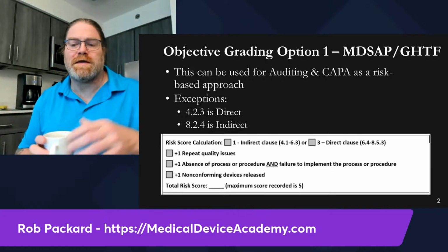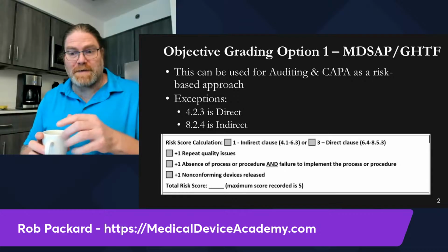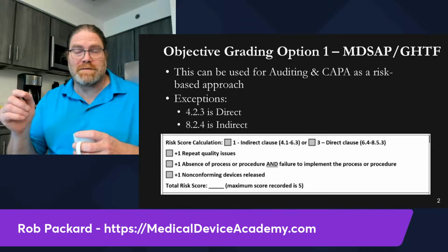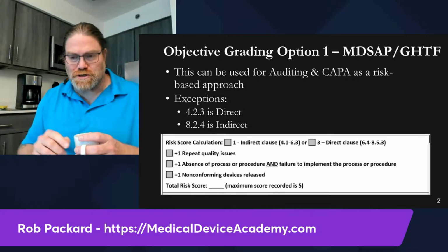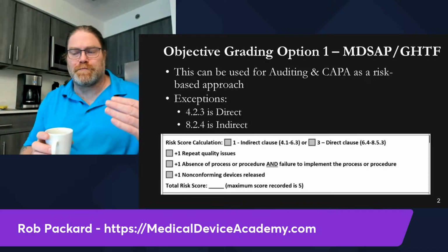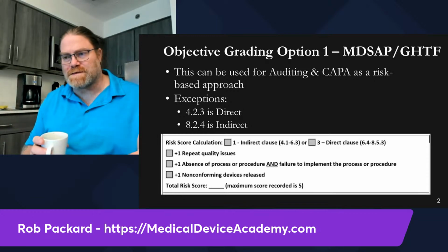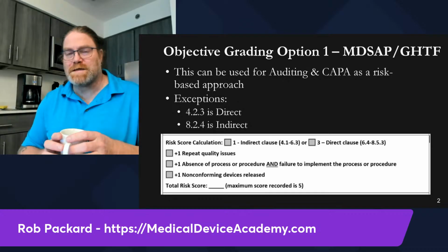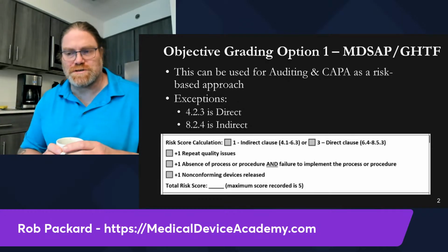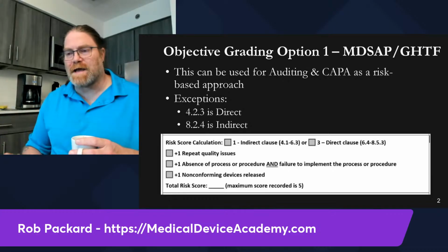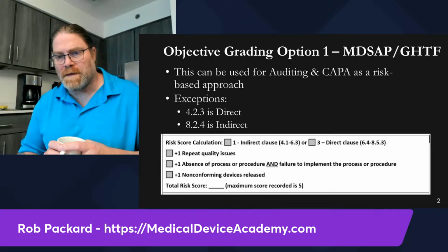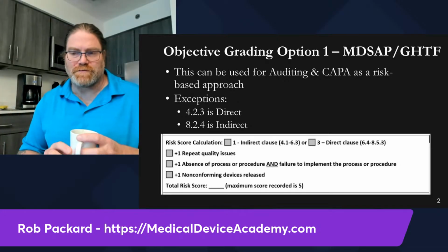This slide here is a copy and paste. Once again, I copy and pasted right from Medical Device Academy's own procedure. And recently I realized I need to make a little correction in this, so I put that in this slide. But this is the objective grading process that is recommended by MDSAP or GHTF. So MDSAP is the Medical Device Single Audit Program. GHTF is the Global Harmonization Task Force. Global Harmonization Task Force was replaced by the International Medical Device Regulators Forum because the regulators didn't want to involve industry anymore.